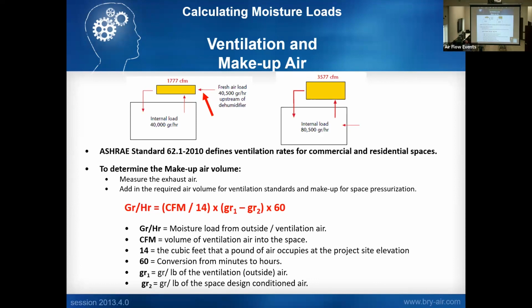It's important. Makeup air is one of the things that typically gets forgotten during dehumidification, that when we're doing our sizing, you know, someone just says, we need you to control the humidity in the space. We'll do the temperature control. But one of the things that they forget about is if they're bringing fresh air into their air handling unit for temperature control, that's adding moisture to my space. If they're doing all return air, that's different. But if they're bringing outside air in, fresh air through the air handling unit, I got to know that so I can add that load. That's a load that's added to the space that I need to handle on my dehumidification side.